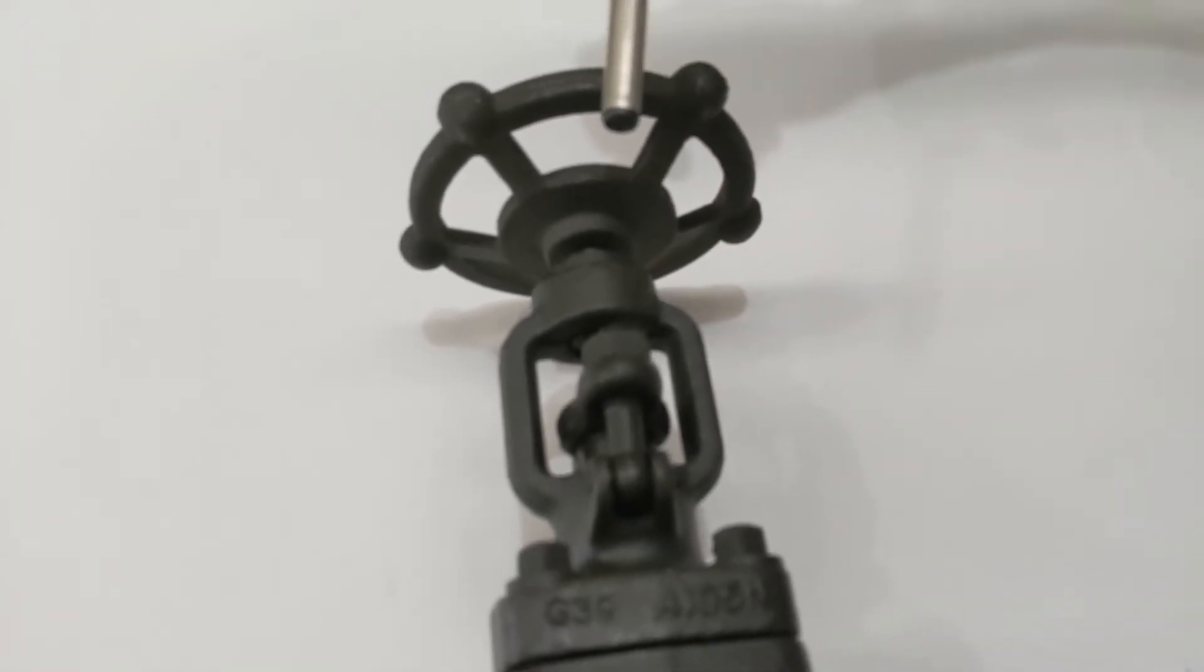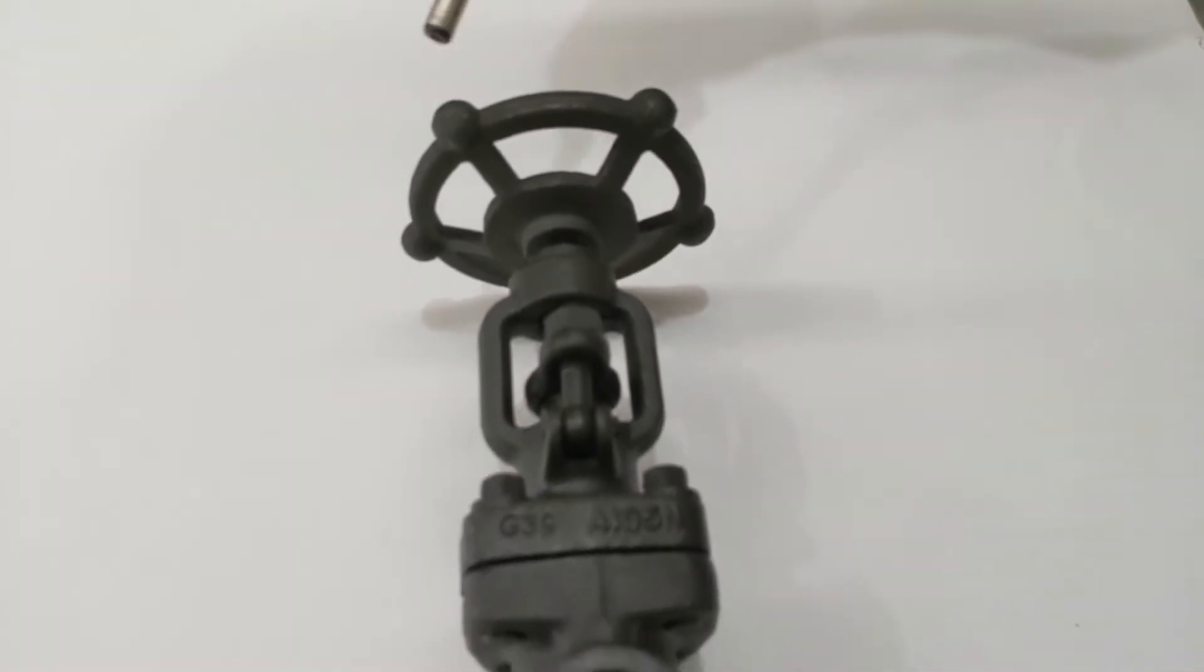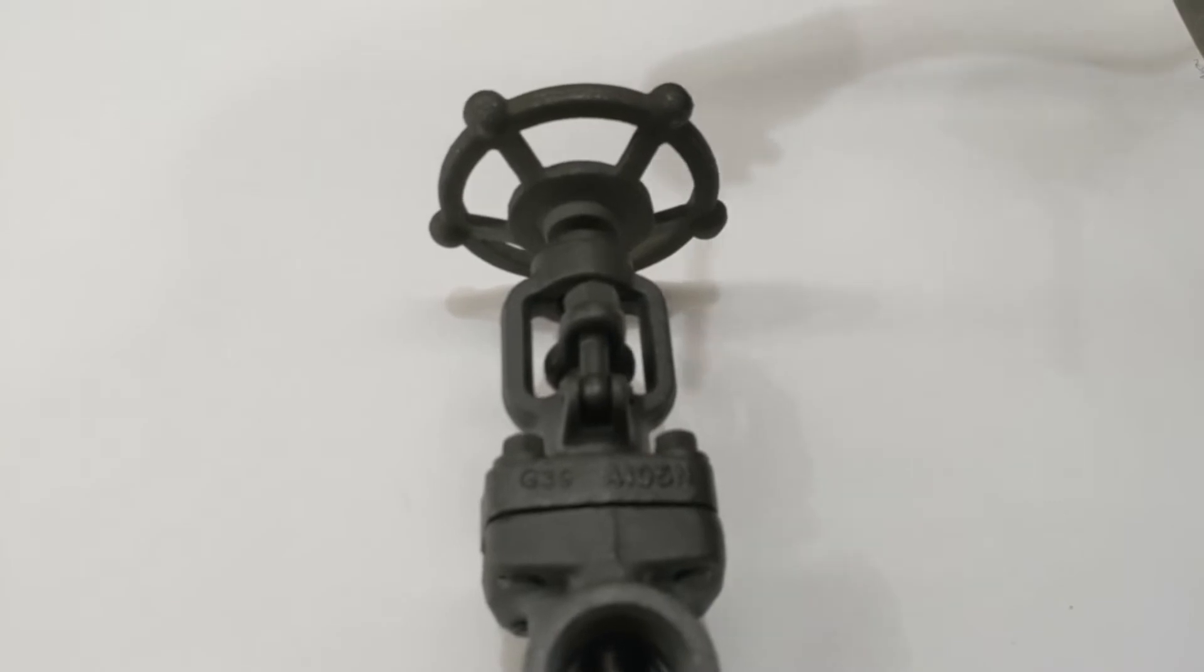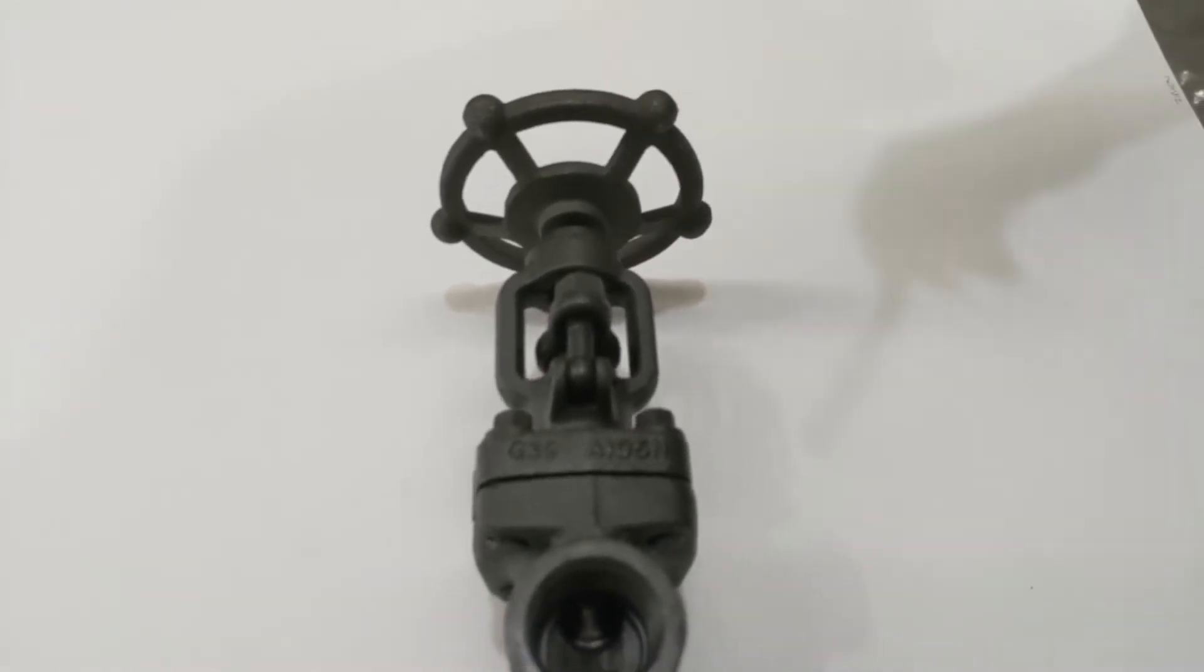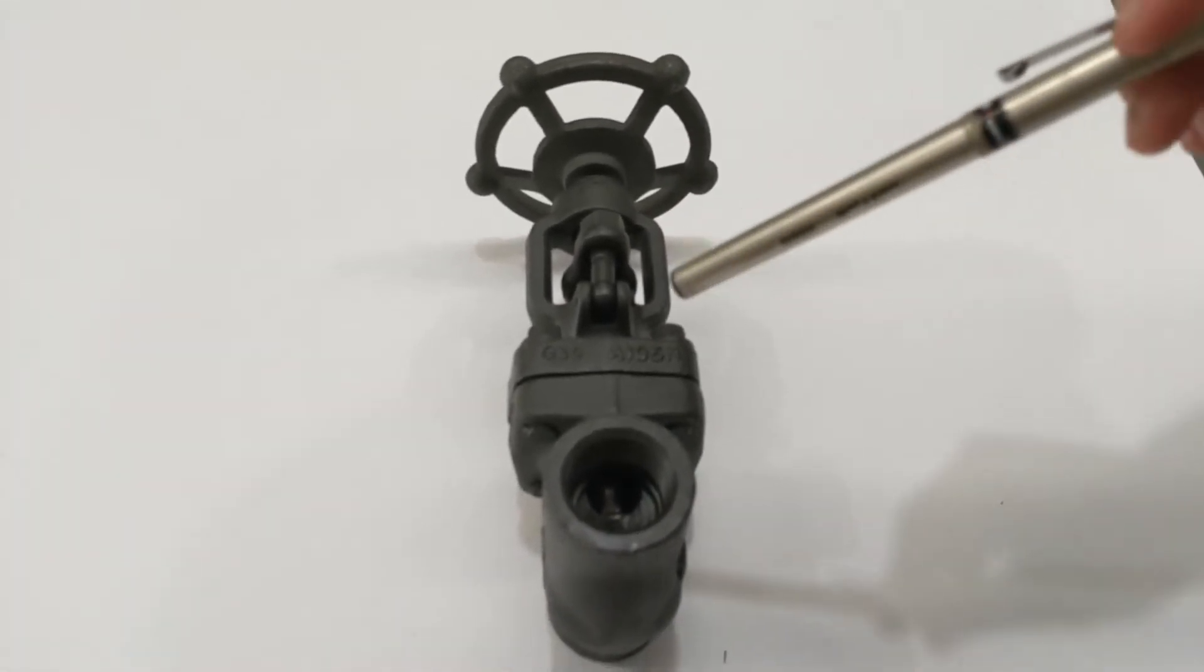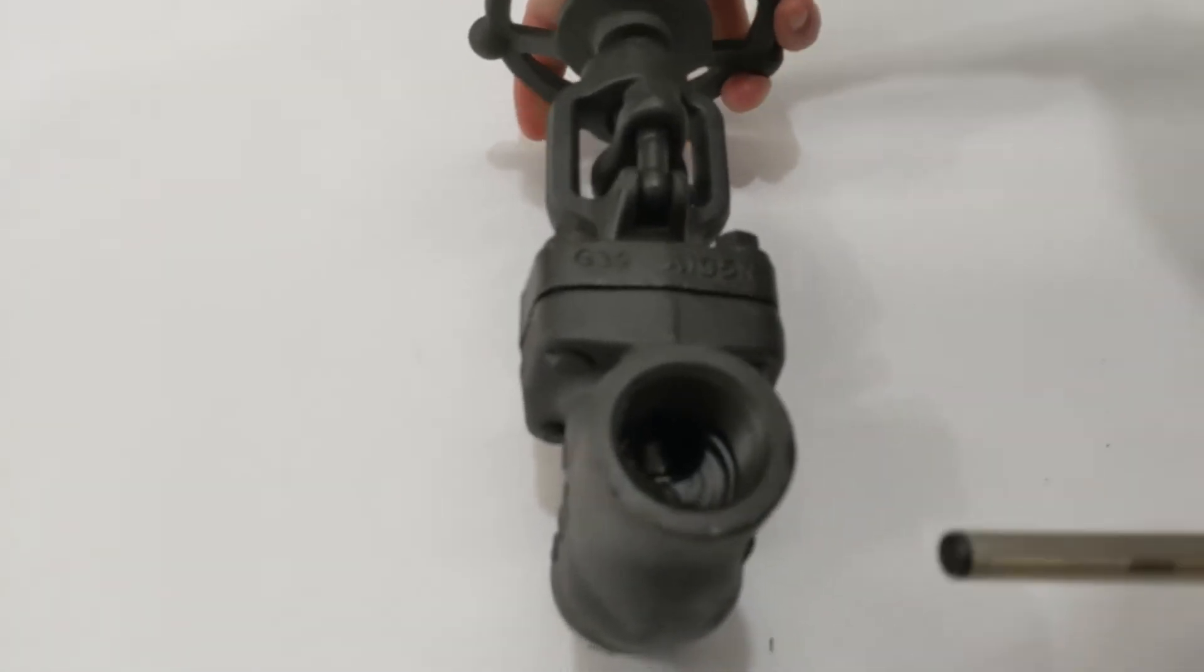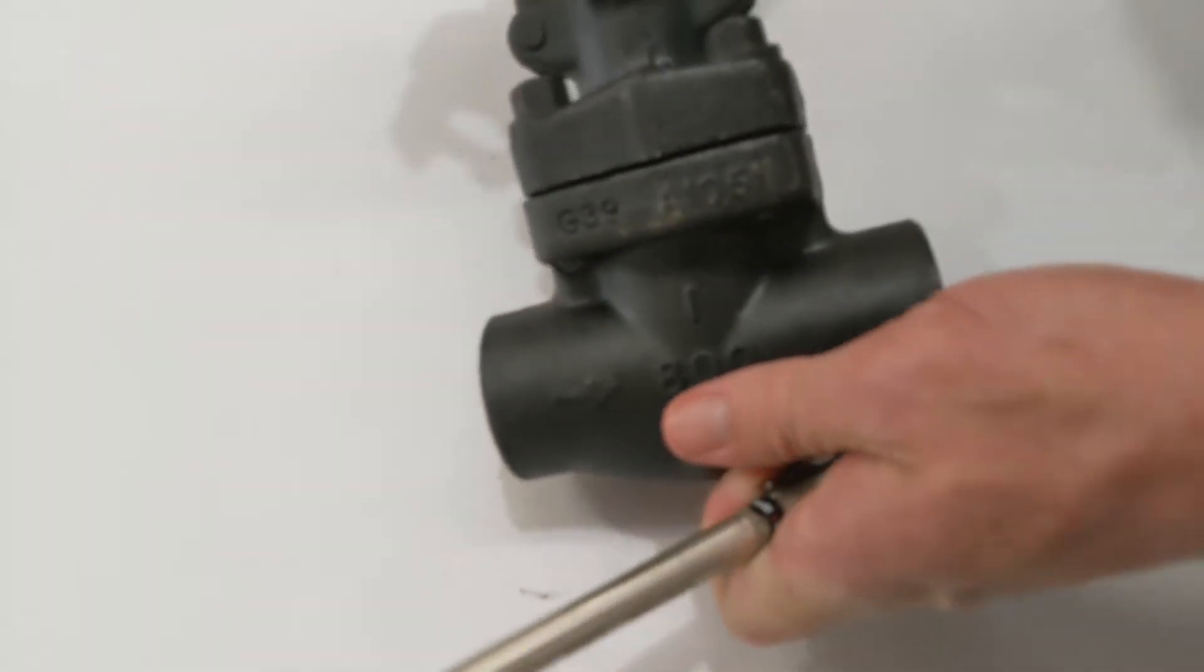It's operated by the handwheel on the top, clockwise to close and counterclockwise to open. You can see down here these globe valves have a direction of flow because you want the pressure to be under seat.